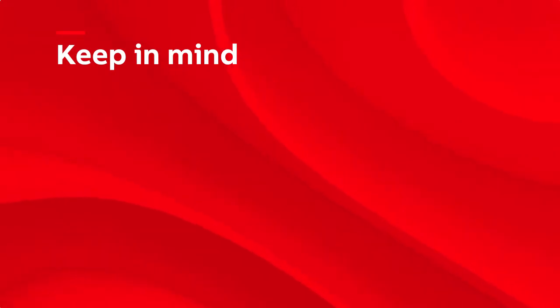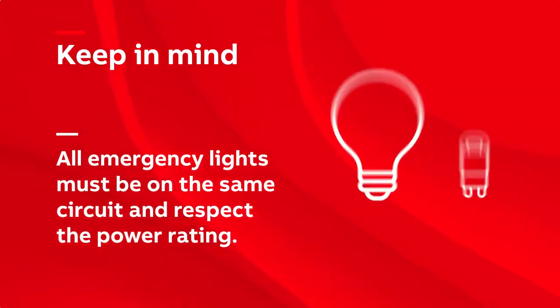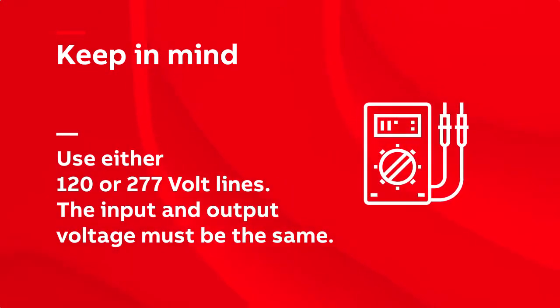For all wiring scenarios, here are some things to keep in mind. All emergency lights must be on the same circuit and fit the power rating. Use either 120 or 277 volt lines. The input and output voltage must be the same.